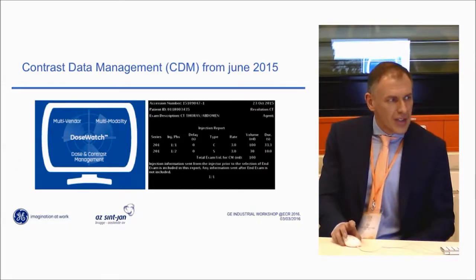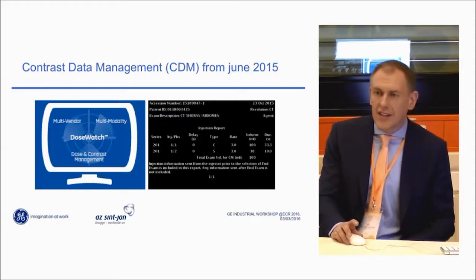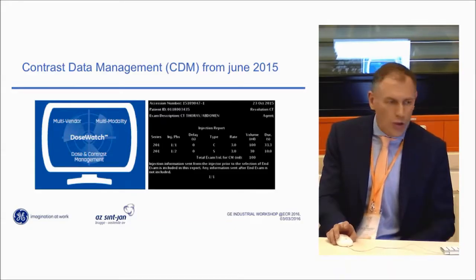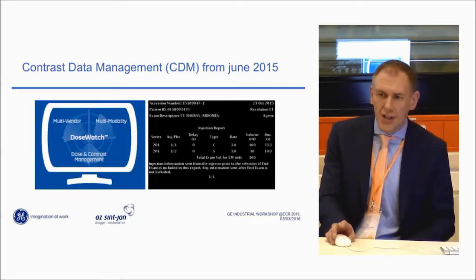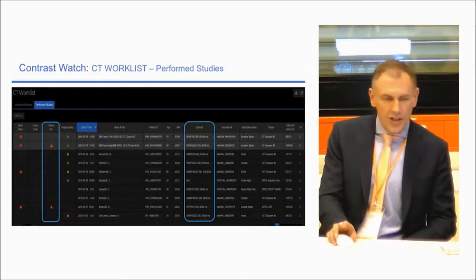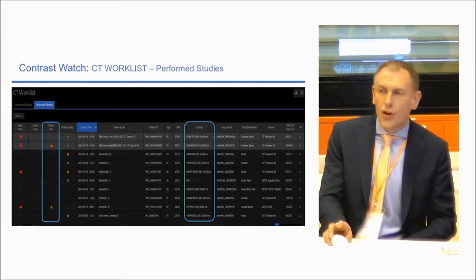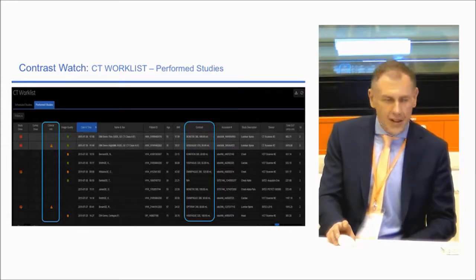That is why we started with ContrastWatch in June 2015. It's fully integrated in the DoseWatch system. This means that now we don't only send a dose report, but also a contrast report to the DoseWatch server and also to the PACS. This is an example of such a contrast report that you can find on our PACS system. When you open the DoseWatch page, you can see that for all performed CT scans, you can find the dose, but also the administration of contrast — what type of contrast and the volume that was injected.